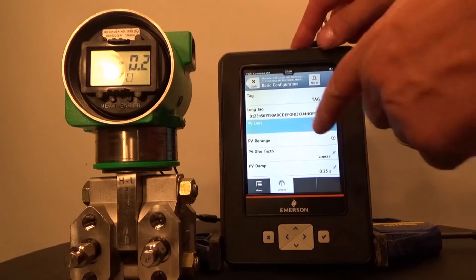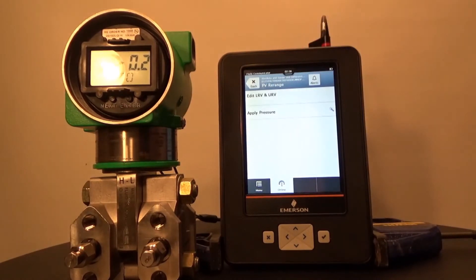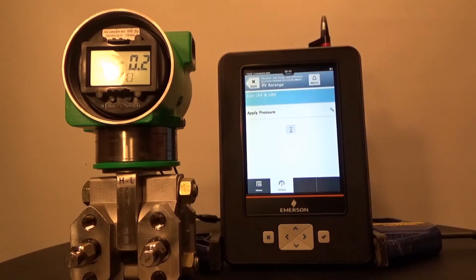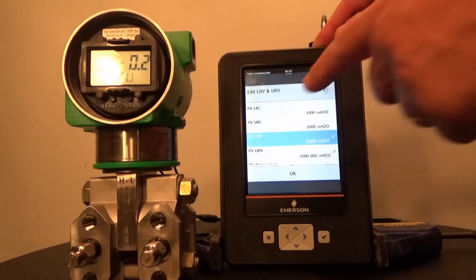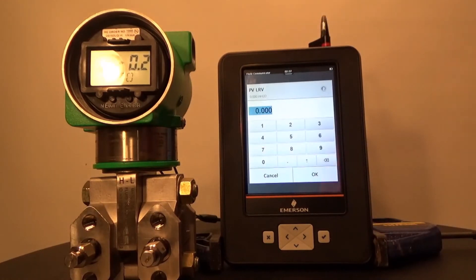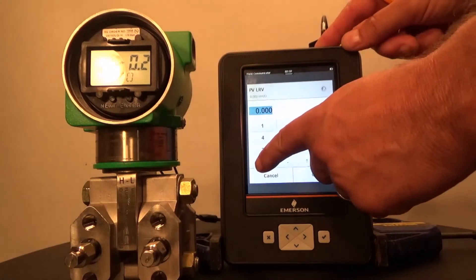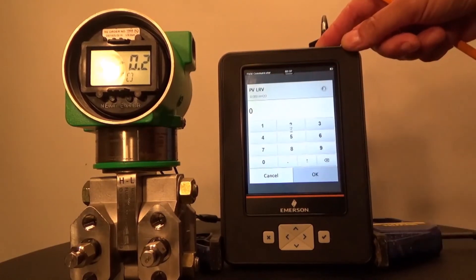From the Basic Configuration menu, select PV Rerange. At the PV Rerange menu, select Edit LRV and URV. From the LRV and URV menu, select PV LRV. In this application our PV LRV is 0 — it's already set to 0, but I'm going to do it just to show you how it's done. Press 0, press OK.